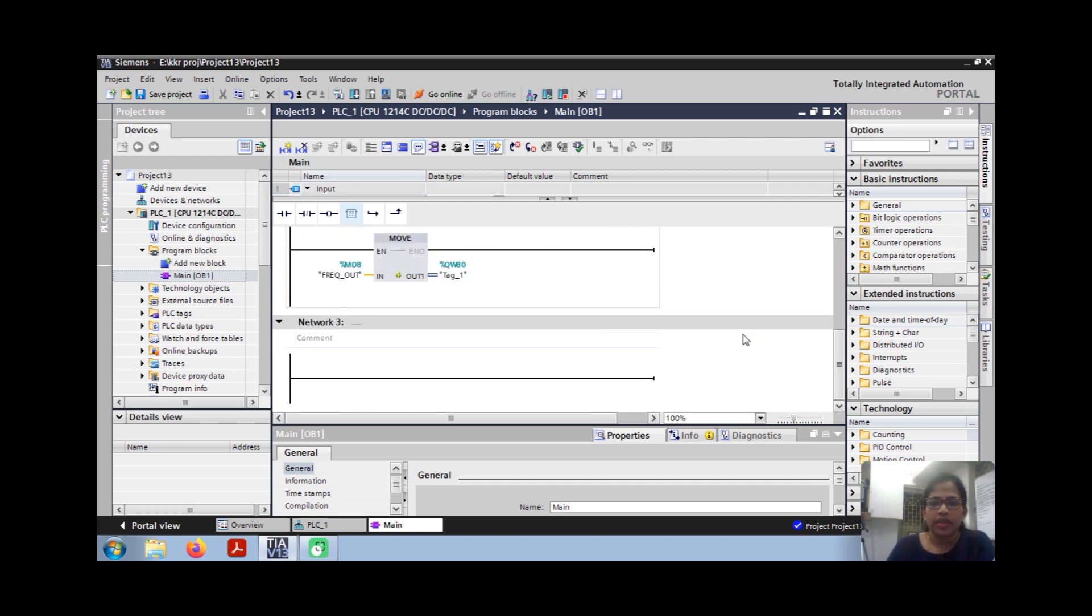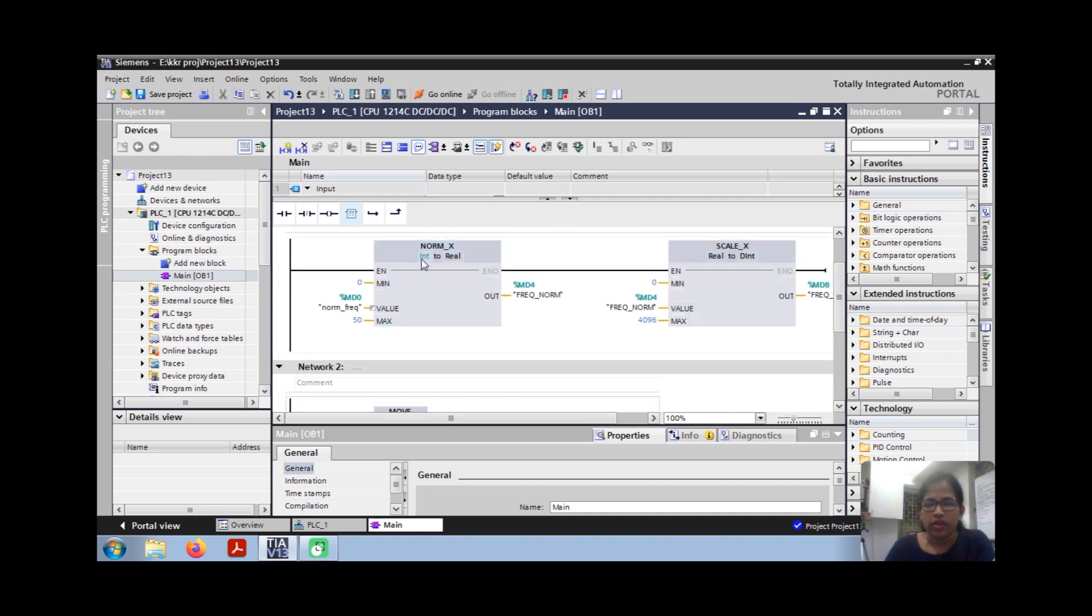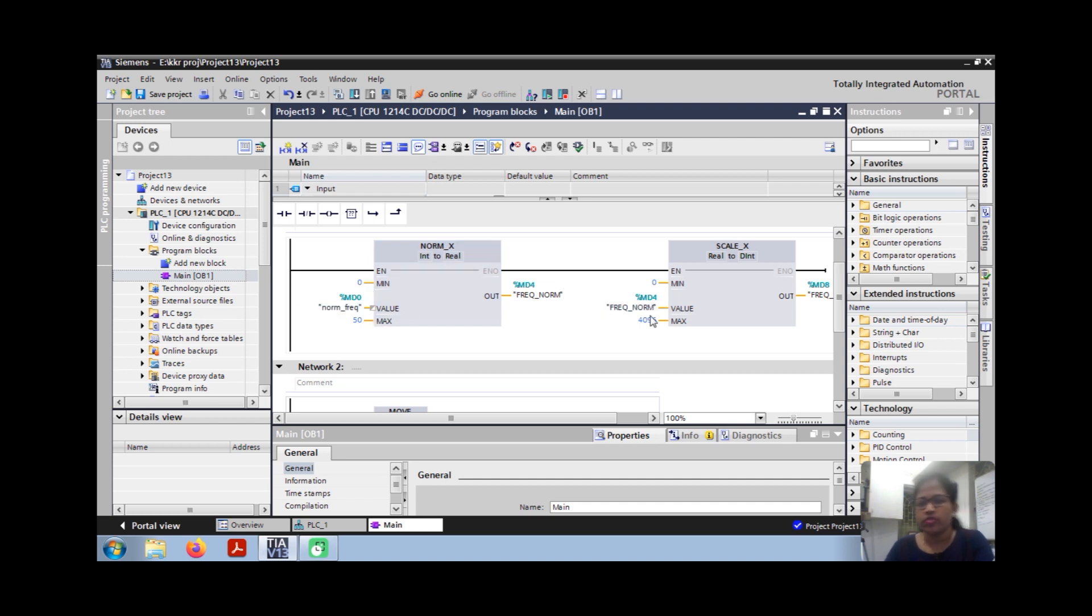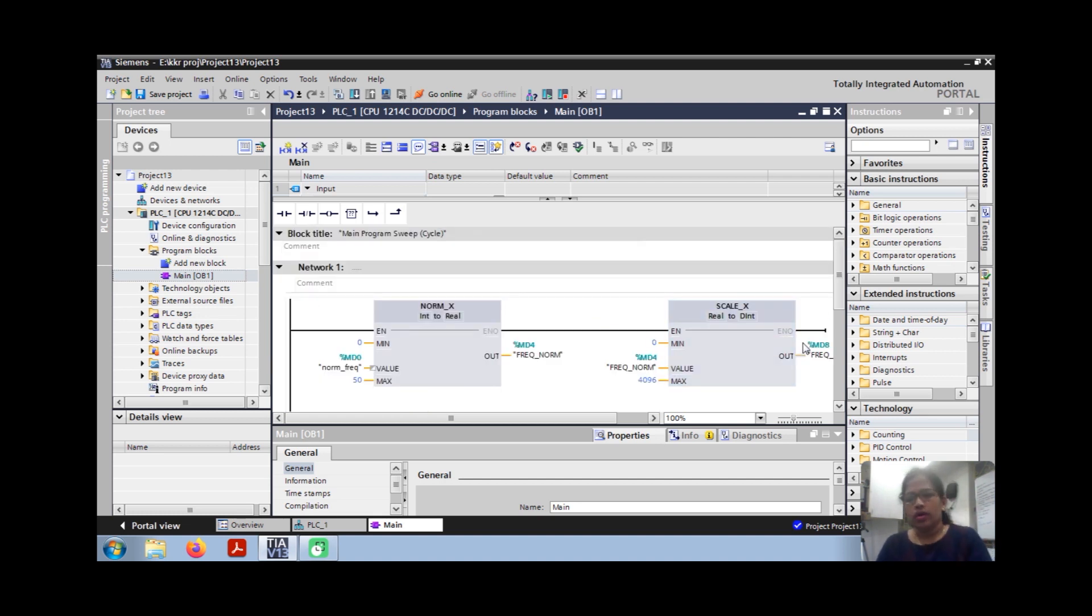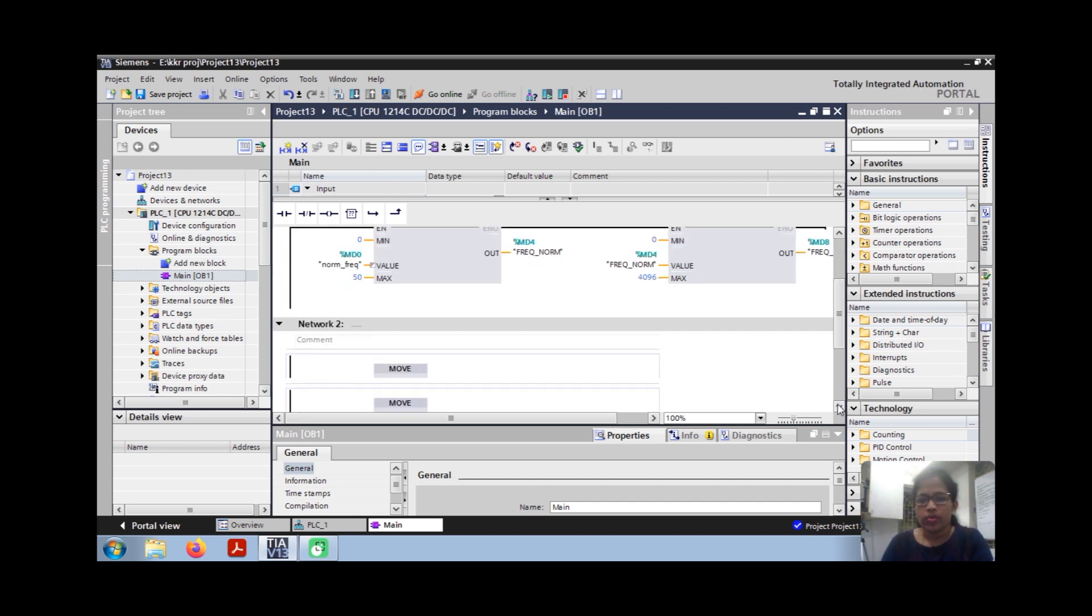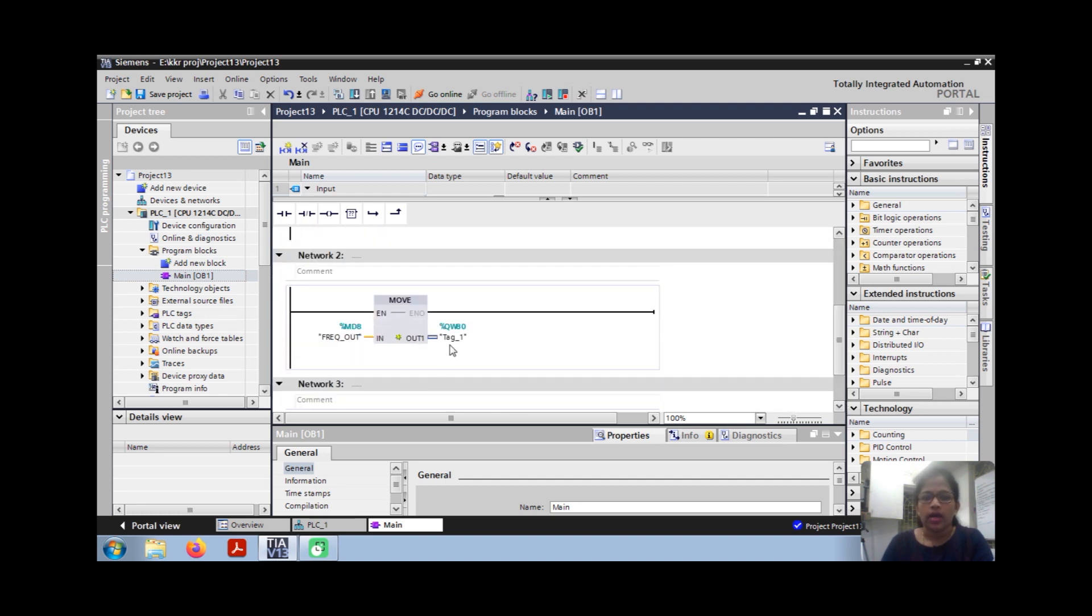So that's all, very easy. First take one empty block, you normalize 0 to 50 hertz to 0 to 4096 for that programming, then you can again move that to QW80.